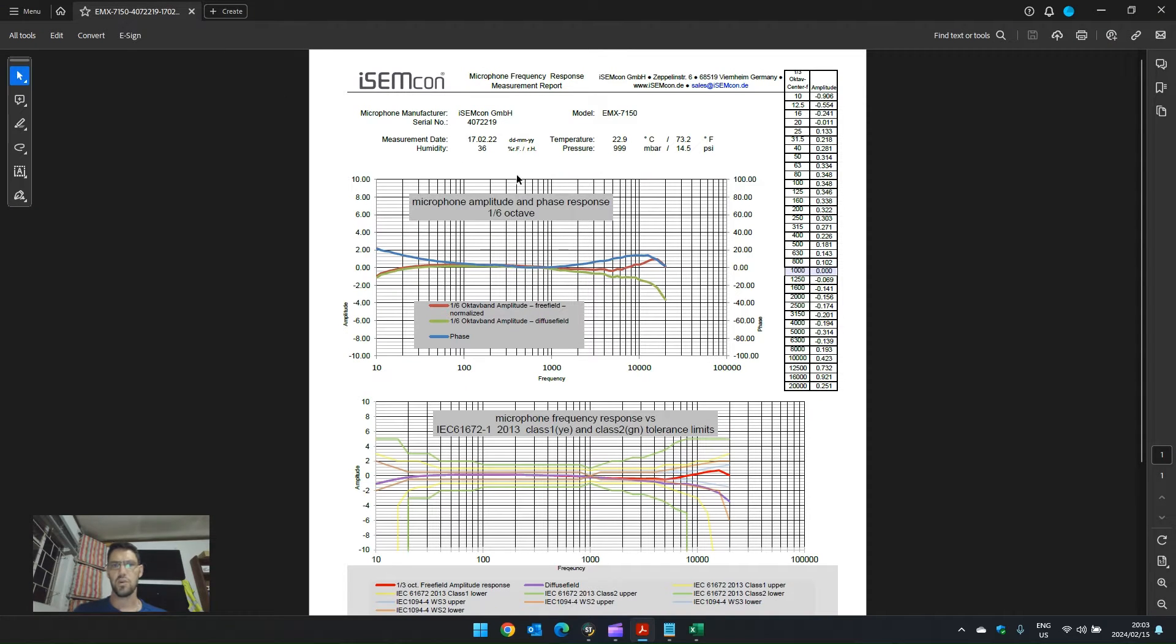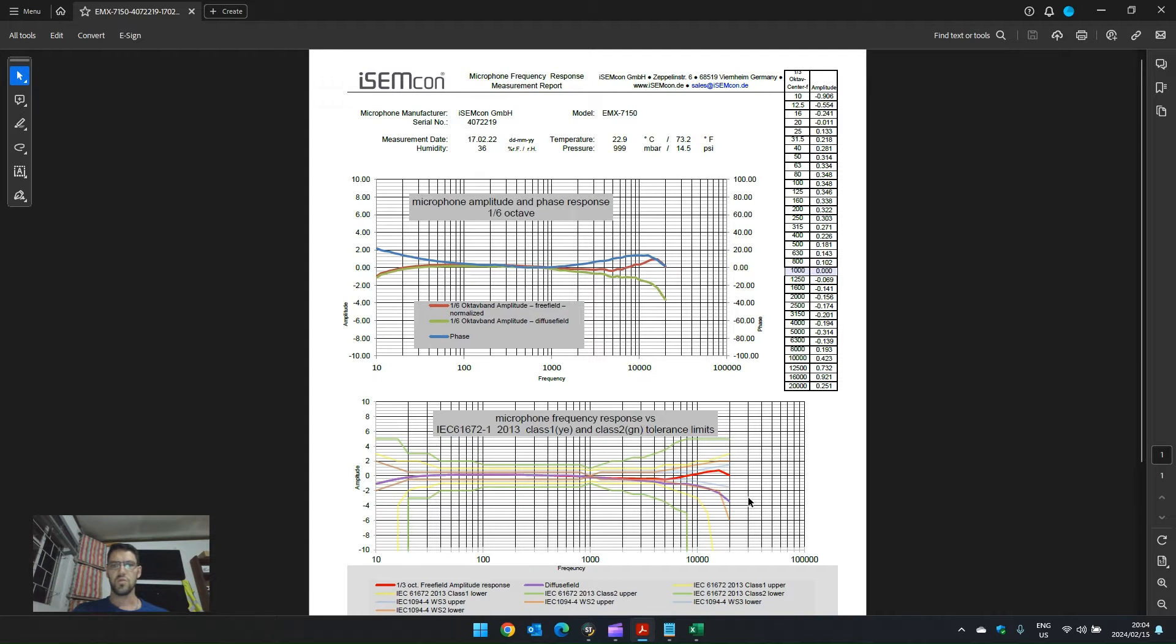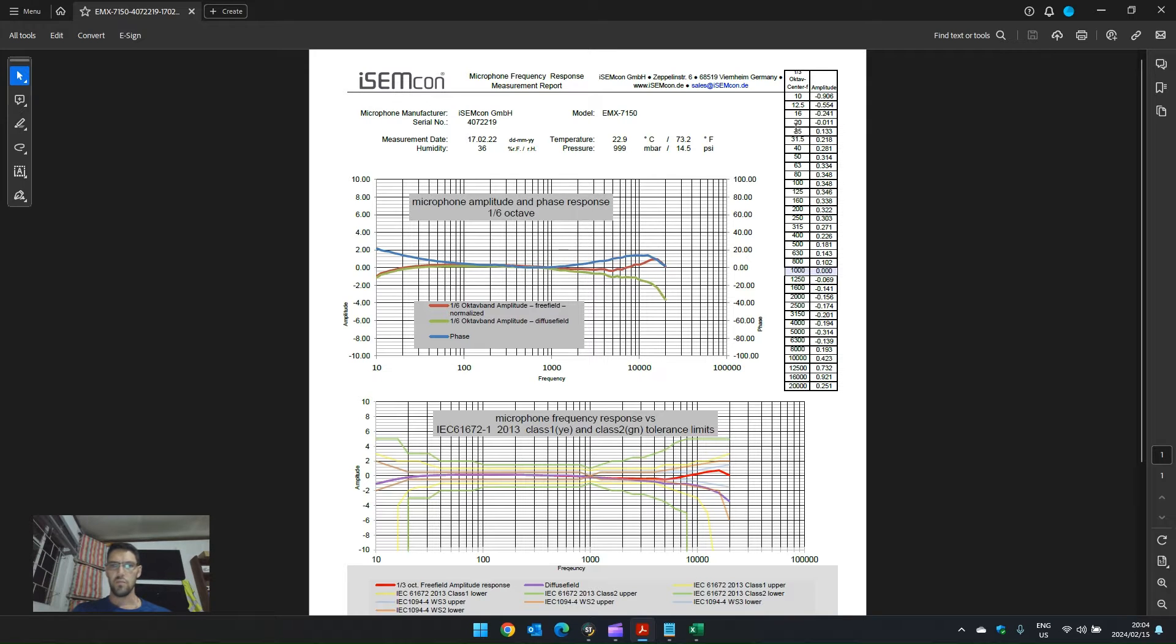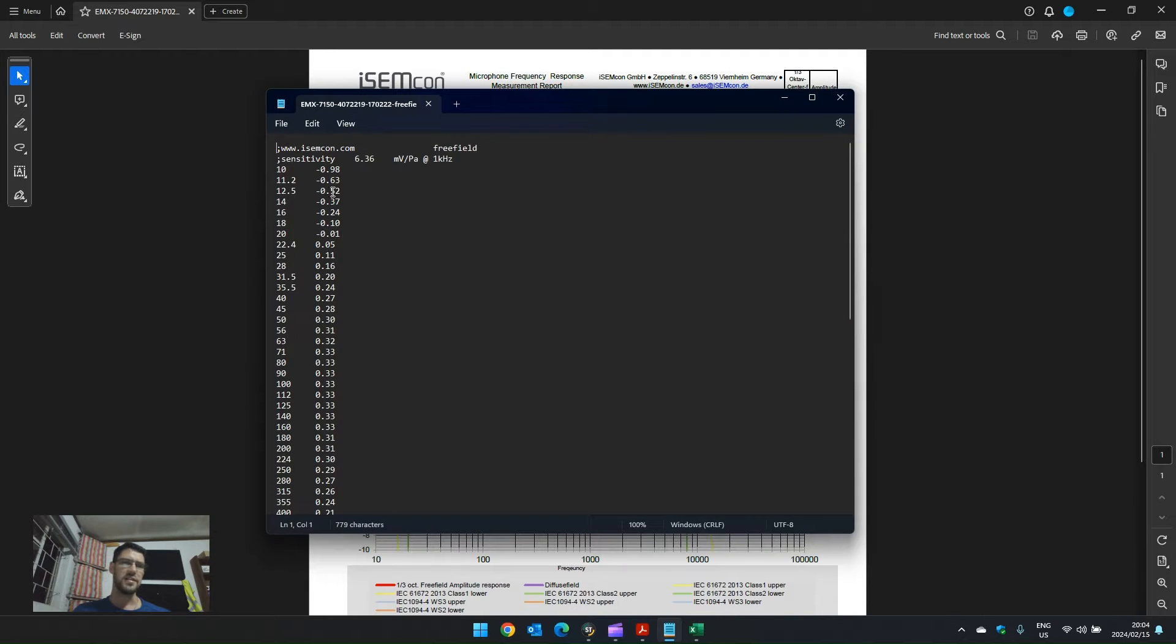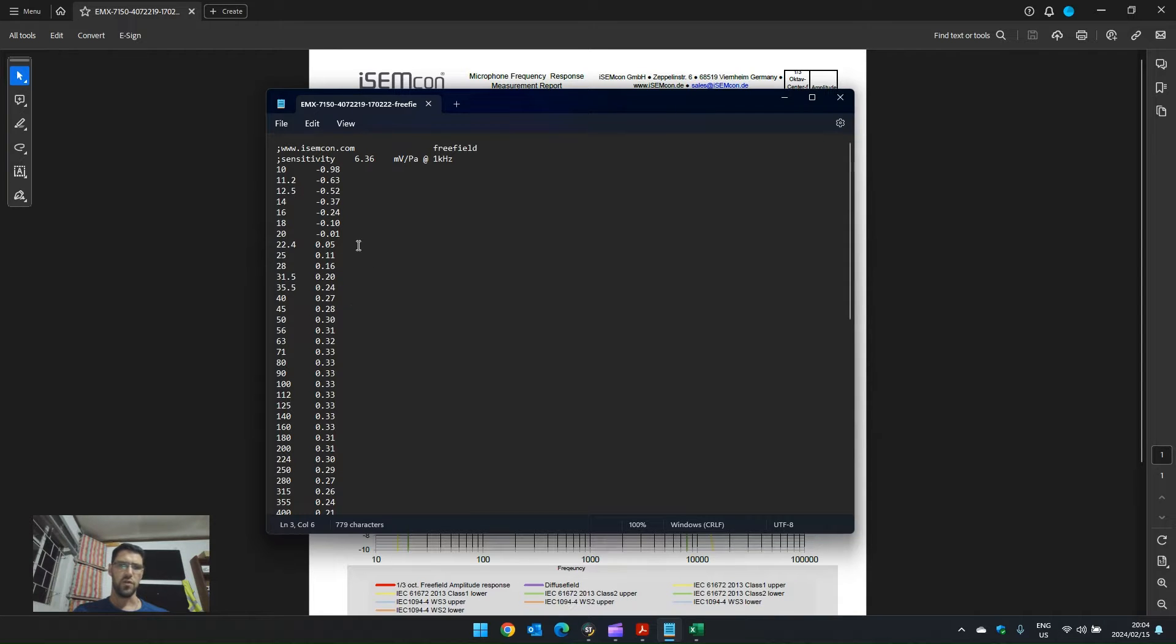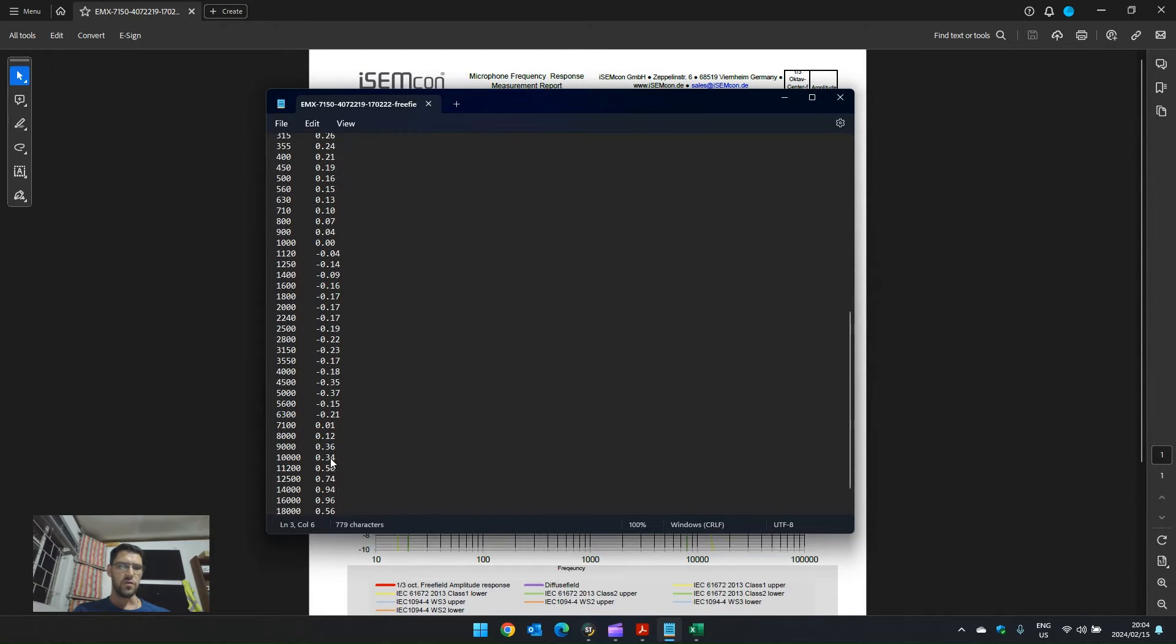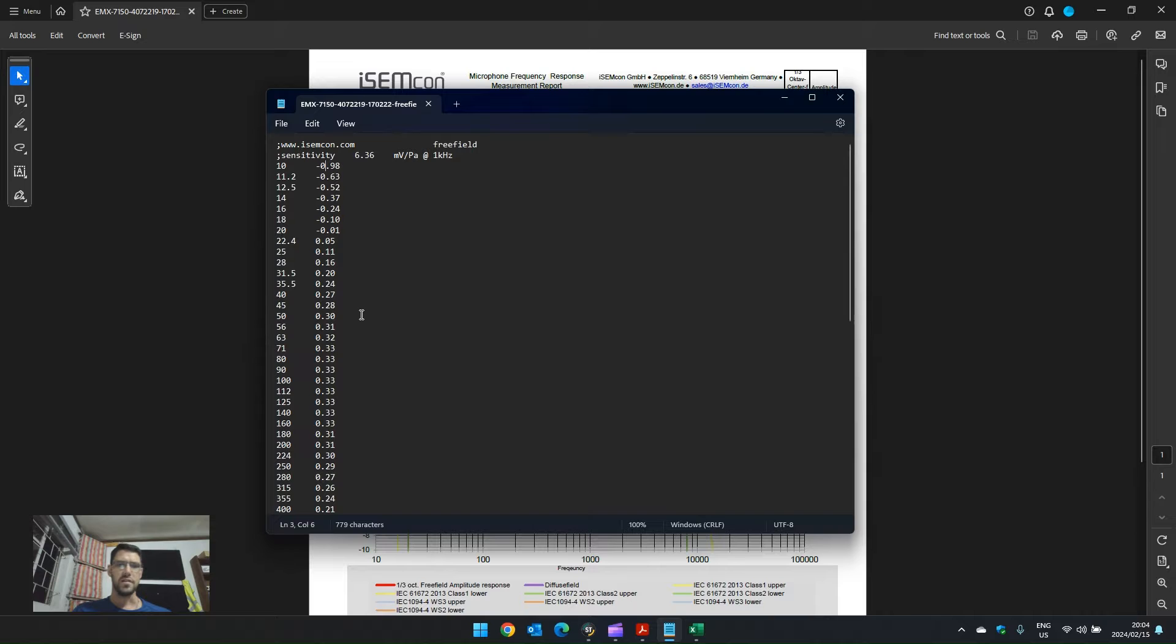Here is an example of the isEMcon EMX-7150, where tests have been conducted to measure the frequency response of this microphone. We can see here how it complies to the IEC standard for a class 1 certified microphone, and on the right-hand side is the calibration that needs to be done per frequency band. A calibration file is usually just a text document that looks like this, with frequency and amplitude offset to compensate for the imperfections in the microphone. As we can see with this microphone, most of the offset is below one decibel.